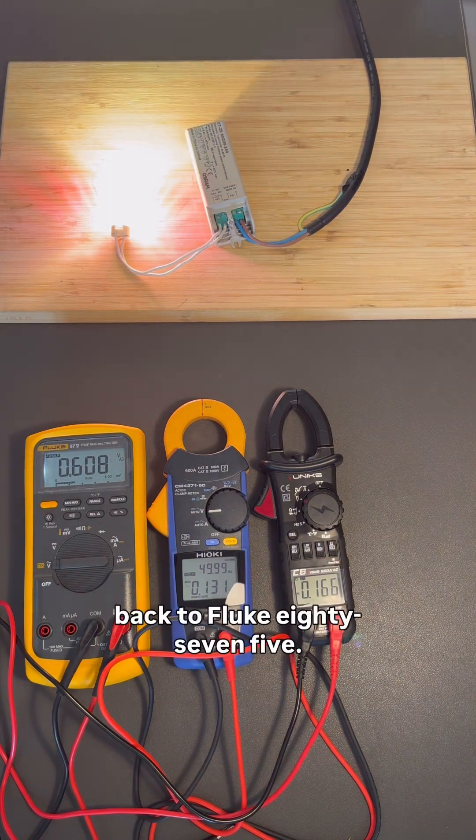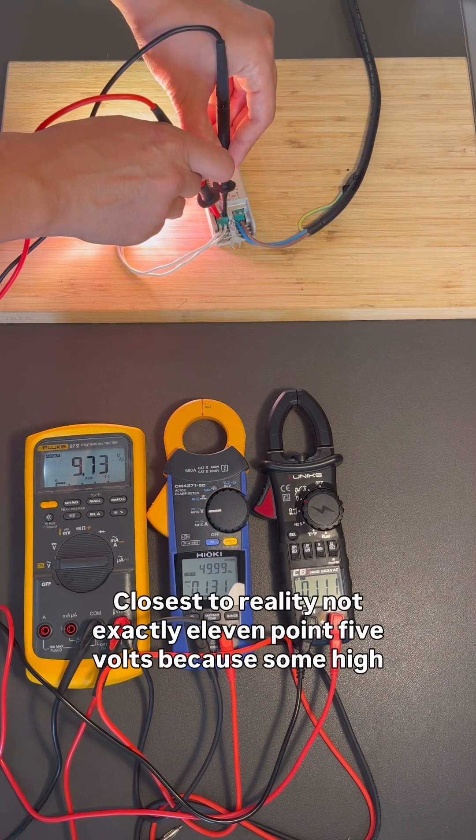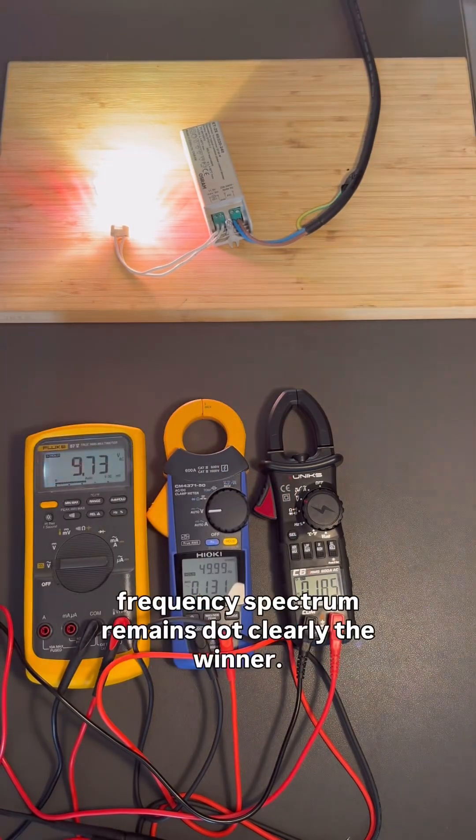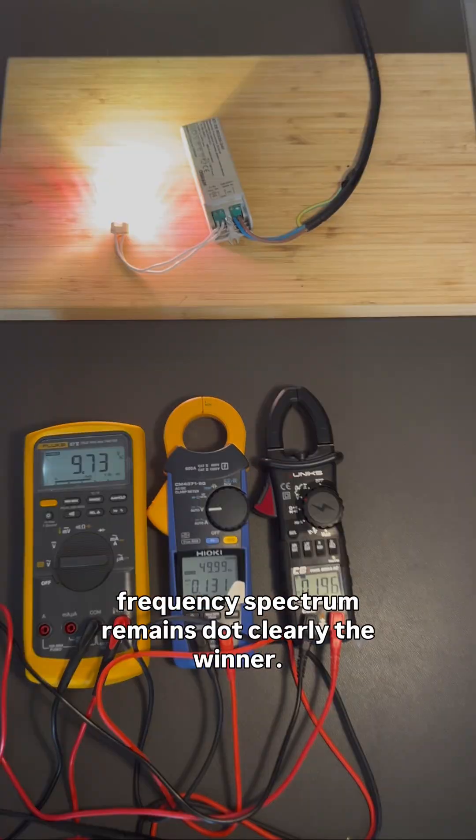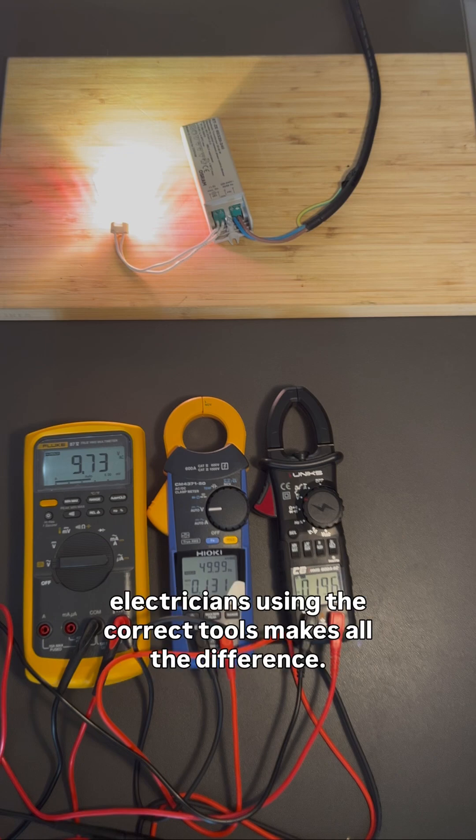Back to Fluke 87-V. Output, 9.73V. Closest to reality. Not exactly 11.5V, because some high frequency spectrum remains. Clearly the winner. Important lesson: choose quality equipment with the right bandwidth. As electricians, using the correct tools makes all the difference.